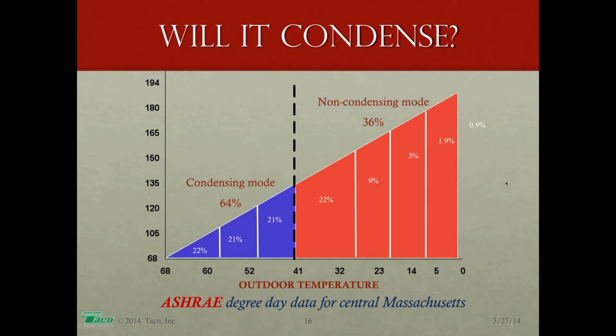Then we go to the condensing mode, 21%, 21%, 22%. If you take a look at this, we are in the condensing mode 64% of the time, the non-condensing mode 36% of the time. This is with fin tube baseboard, boiler firing up to 180 degrees with outdoor reset.